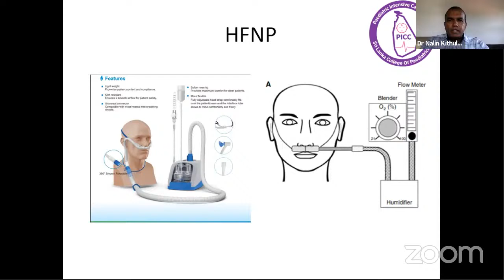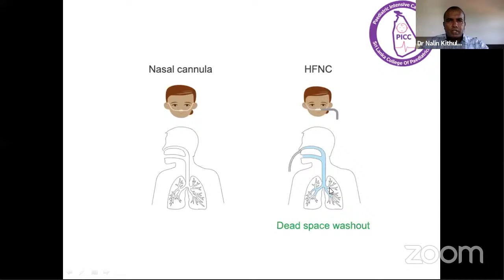As Deshan clearly mentioned, there's a flow meter, oxygen blender, humidifier, and the patient interface. And two important aspects, Deshan already discussed, but I think it's important to revisit. When you're using a nasal cannula, this dead space is not washed out. But in high flow nasal cannula therapy, since you're using a high flow, this dead space is washed out. This is very important when you're thinking about carbon dioxide removal. So carbon dioxide washout in high flow nasal prongs, the flow dependent carbon dioxide clearance, obviously.